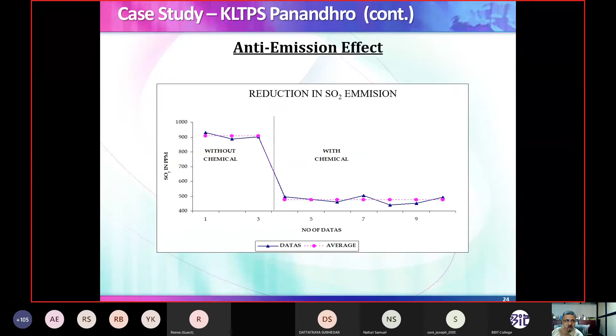These are the results. Auxiliary power consumption is reduced by 3.21%. Boiler efficiency, because it is lignite with high moisture, is quite less, 74% as compared to grade F coal. So the improvement is 2.75%. Generation efficiency improved by 2.51%. SO2 reduced by 23.78%. And particulate emission reduced by 30.92%. So this is the result with SCA fuel additives. And fuel saving is 13,788.5 tons per year.